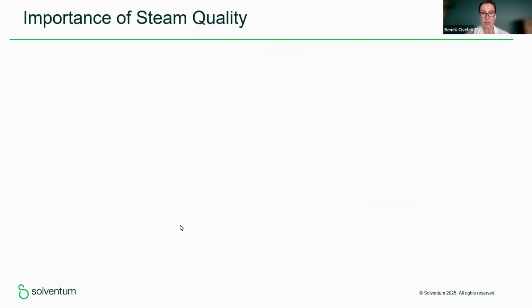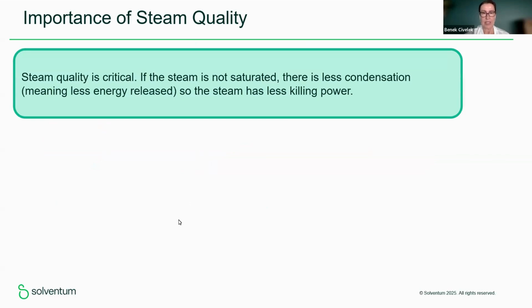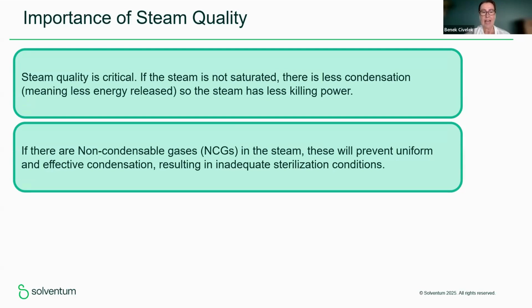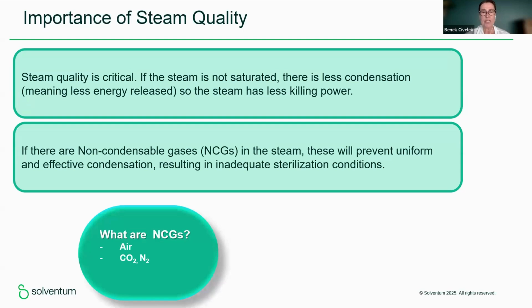We understand the importance of steam quality for successful sterilization. It is critical because if the steam is not saturated, there will be less condensation, so there will be less energy release to kill the microorganisms. So this sterilization will not be successful. And we are talking about non-condensable gases in the steam. These gases will prevent the uniform, effective condensation, and they will affect the quality of sterilization. So what are these gases? In fact, these are what is present in the air: carbon dioxide and nitrogen, which cannot condense under steam sterilization.